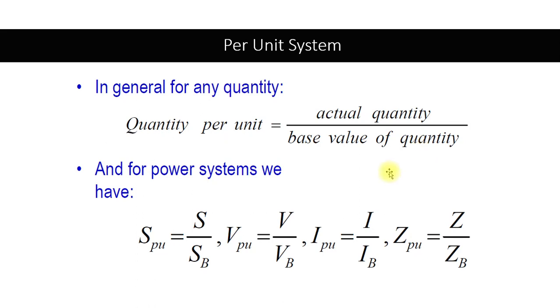For the power system, all four quantities can be written in per unit form as follows: S per unit equals S actual divided by S base; V per unit equals V divided by V base; I per unit equals I divided by I base; and Z per unit equals Z divided by Z base. Every quantity divided by its base gives the per unit quantity.